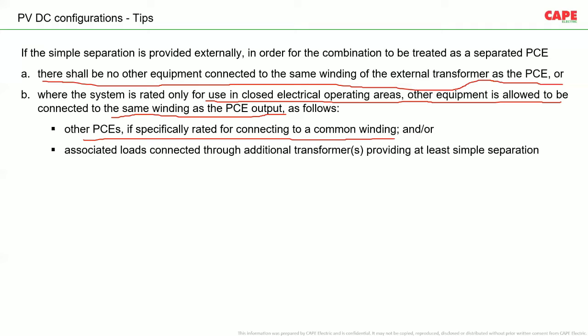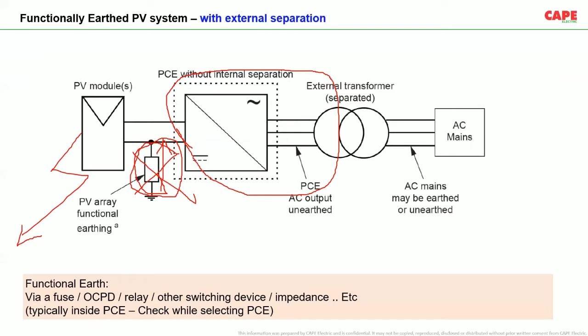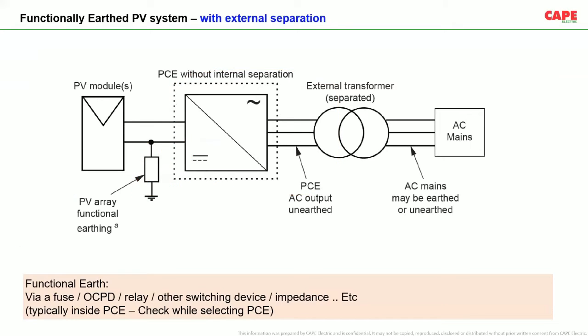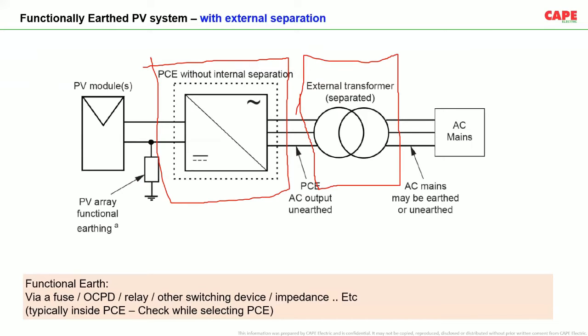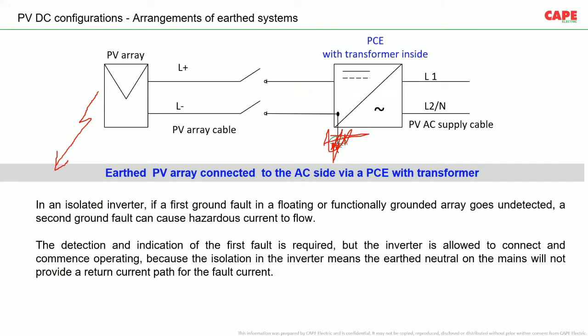Now, where is this applicable? Let me take the picture. Say, for example, this picture: you have an isolation transformer for your solar PV. The standard recommends this isolation transformer must be exclusive to this particular PCE. If you want to use the same isolation transformer for multiple PCEs, then that PCE should have some extra safety measures. So you have to check the PCE manufacturer's catalog and find out whether a PCE without internal separation is allowed to connect to a common transformer. You have to be careful in that particular case. I'm sure most of you are already doing it. This is how the earth fault protection is achieved.